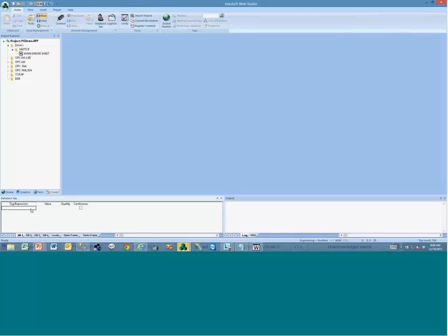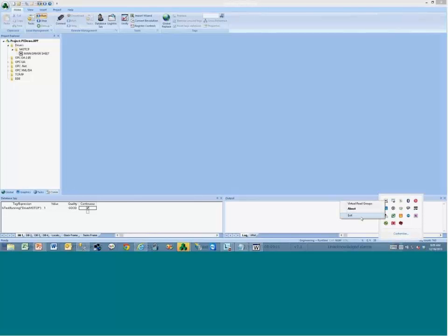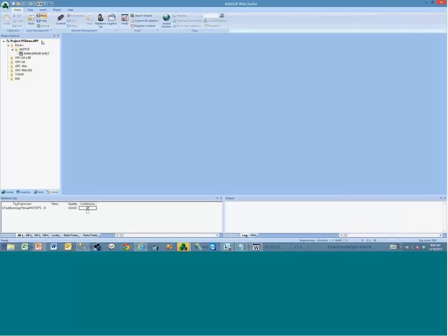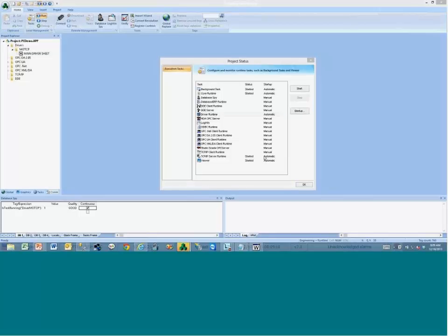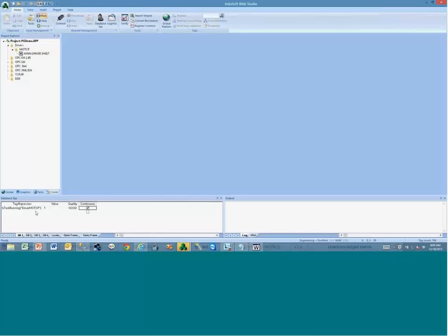There are three functions in InduSoft Web Studio that allow you to manipulate tasks, including drivers. One of them is a function called isTaskRunning, and you can verify if each one of the InduSoft tasks is running or not. In the case of a driver, it is the word driver and the name of the driver you want to monitor, for instance Modbus TCP. If I use the syntax isTaskRunning driver Modbus TCP, it returns 1 if the driver is running, or 0 if the driver is not running. So if I close the driver, the function returns 0. If I run the driver, the function returns 1.